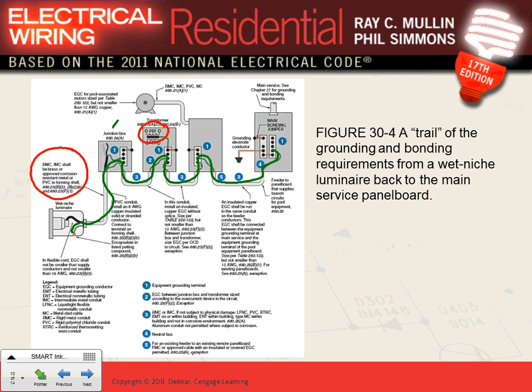There are two types of luminaires: dry niche luminaire and wet niche luminaire. It talks about basically the bulb itself being completely immersed in the air and in the water if it's wet niche, or it's dry. If it's dry, you have to have another way of getting into the bulb from the other side. Either way, you have to have a number 12 copper grounding conductor going to the fixture, and an isolating transformer. You have to put in a GFCI. Your ground has to go all the way to the panel, to the source. Any comments, any questions? You have to use PVC. Most of the time we use PVC. Rigid if you have, or PVC schedule 80 if you have physical damage. This is mostly for installation, but for you as a project manager, it's really nice to know. Any comments, guys? Any questions about that before I move?